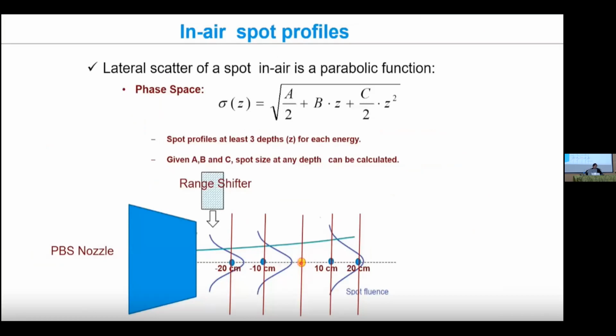One thing that's important, and one of the key acceptance tests that you'll be doing, is the in-air spot profiles. What this means is, what does the spot look like when it's not interacting with the patient? It's kind of as pure as it can be, so kind of in air. And you have to take these measurements at different points. There are different tools that you could use, and we'll talk about the tools in a bit. But these are things that are going to start characterizing the beam and what's coming out of the machine at every single energy. Because again, the machine can produce many energies.